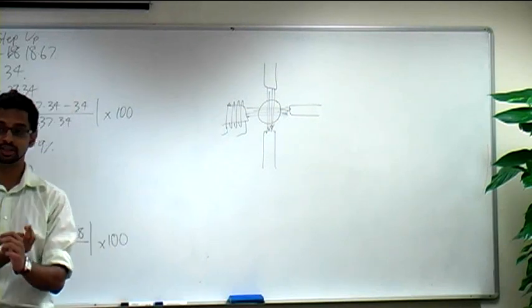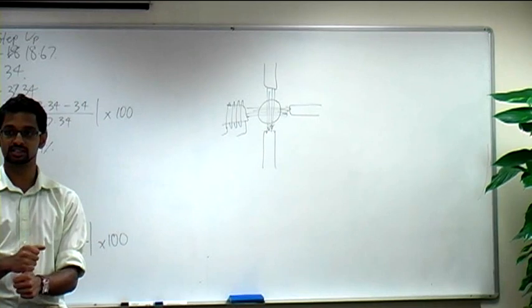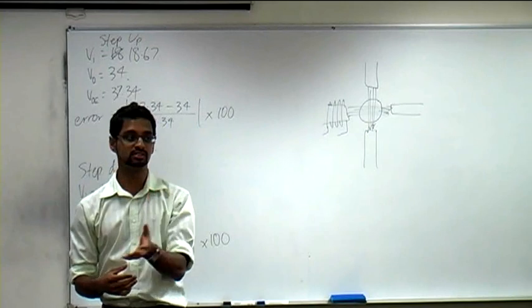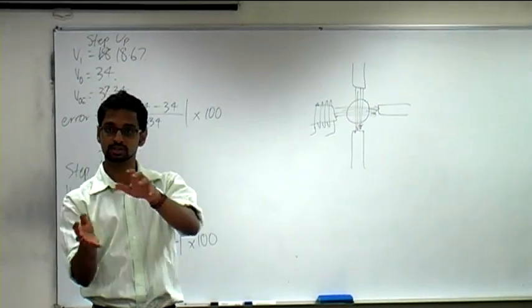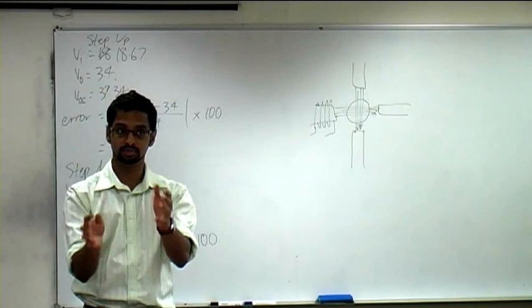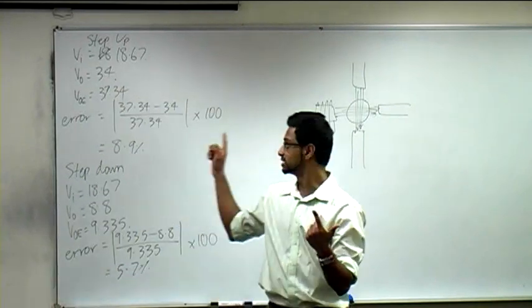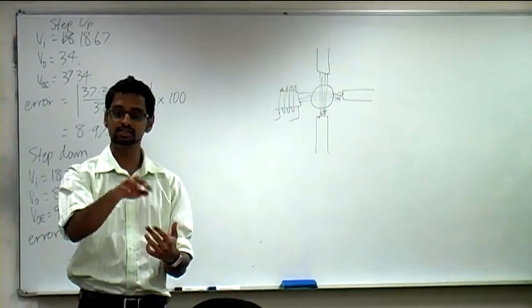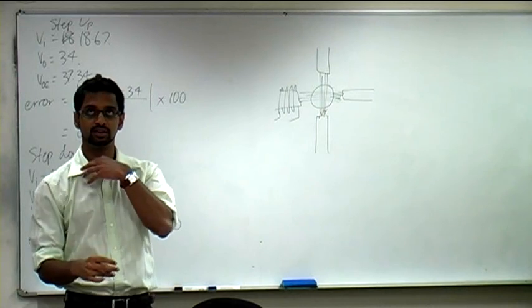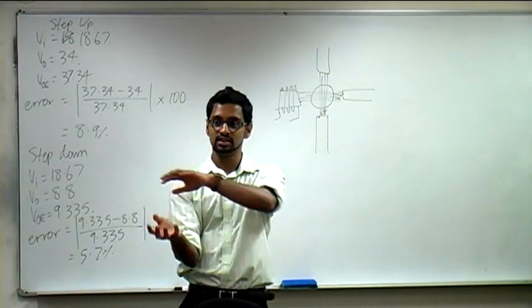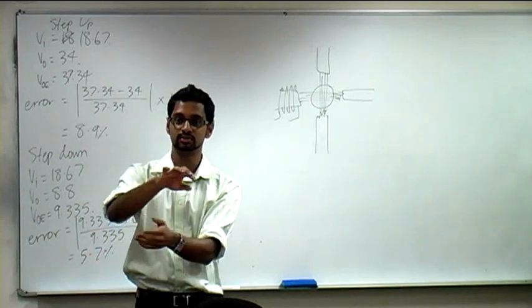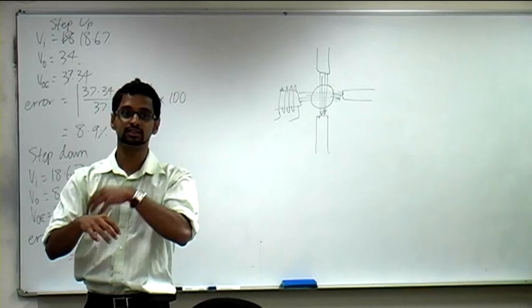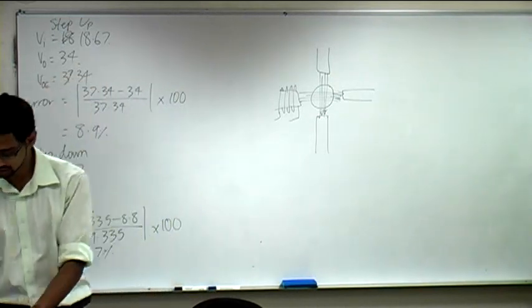And that's by Lenz's law, right? We normally have an EMF induced to oppose the change in flux. The change in flux is rotating like this. To oppose that, we're going to induce the current. This induced current is going to cause the motor to rotate by the motor effect. We have a current in a magnetic field, in an external magnetic field, that's going to cause the rotor to rotate. The motor is going to try and rotate to catch up. If it catches up with the rotating magnetic field, it no longer needs to experience a changing flux.